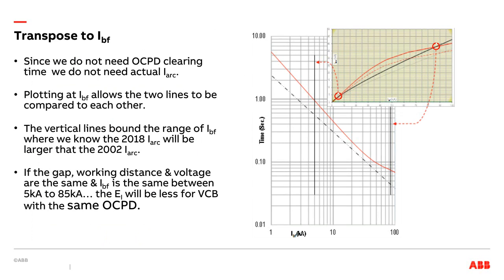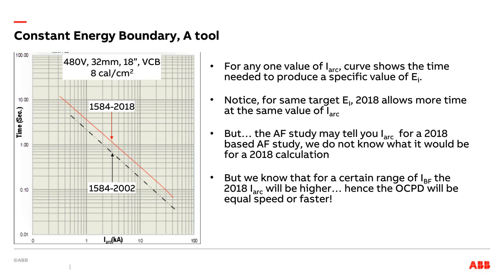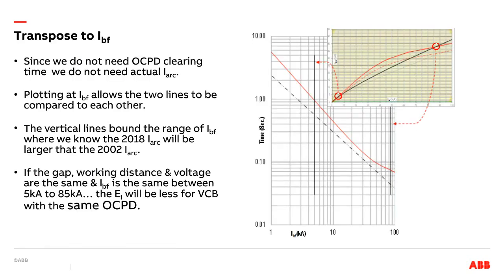The problem is that for this chart, you do need the exact arcing current, and you're not going to have that unless you're doing an arc flash study. What you do know is your bolted fault current. If you plot the exact same 2 lines at bolted fault current, which is not the normal way people use that graph, it's a different way. But I'm suggesting that this transposes all of the values to bolted fault current, which you do have because you know the short circuit in your system. And if you look at your old arc flash study, that information should be available to you, or a short circuit study. You have that information, regardless whether that study was done last year or 5 years ago.